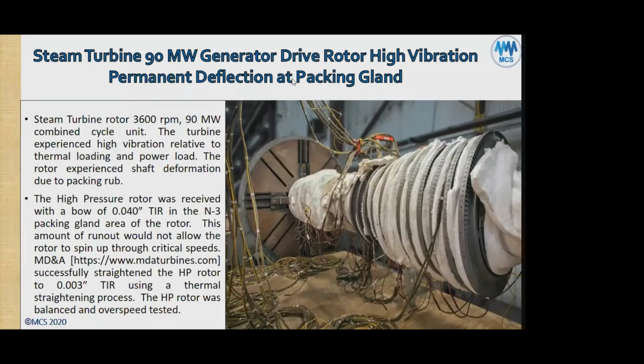Later on, if that doesn't do the job, they're going to have to also add heat and then use a hydraulic press with heat only, uniform heat on it, to straighten out the bad kink in the rotor. So they were able to successfully straighten it within 3 thousandths of an inch, total indicated reading, using a thermal straightening process. The HP rotor was then high-speed balanced and overspeed tested, and it was put back in service with no problem.